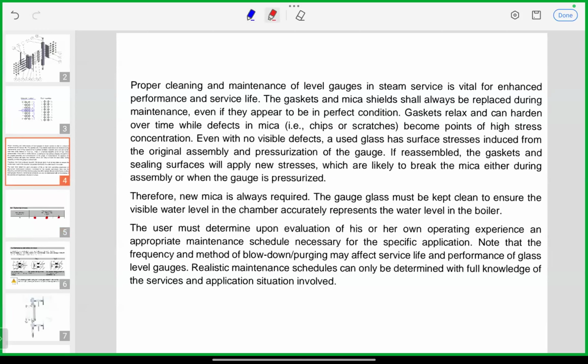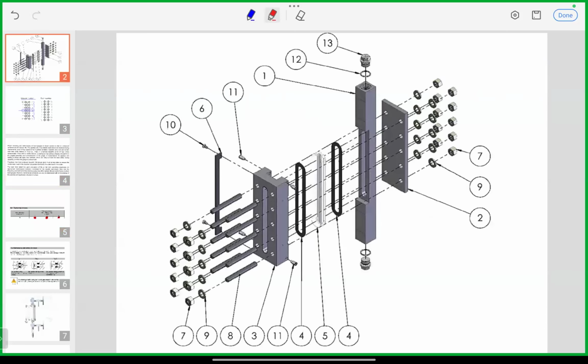Very important step: after overhauling your gauge glass, when assembling it, you have to only hand tighten it. After hand tightening, put the glass on the boiler, connect it, and let it remain in that condition for at least 30 minutes to 1 hour, so it comes to the same temperature as the boiler.